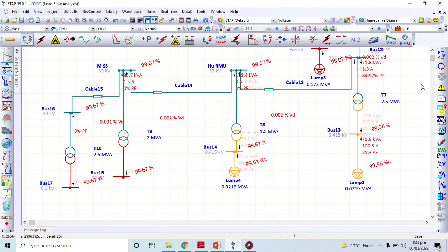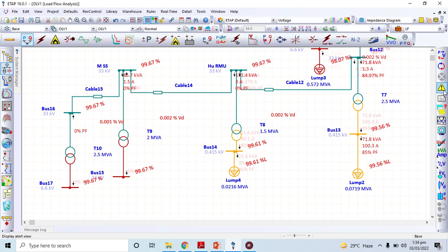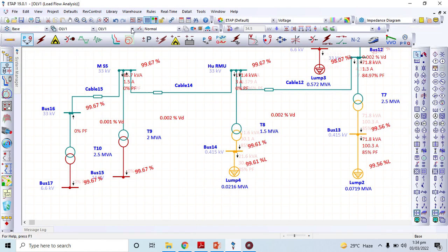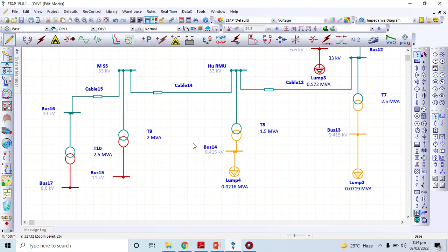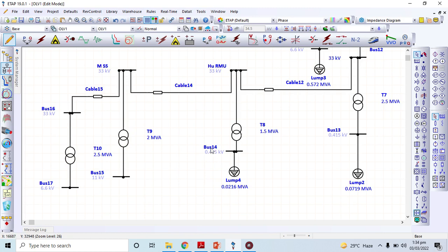Now we have a triangle symbol — this means some values are in alert mode but not in emergency mode. Alert mode means it is near loaded but not completely loaded. To check this transformer's maximum sizing I need to connect some more load. If you have a problem understanding this color scheme, just change it to phase-to-phase. In ETAP, when a component is overloaded it shows red color, and when it is near overloaded it gives purple color. Better to use the black and white diagram.